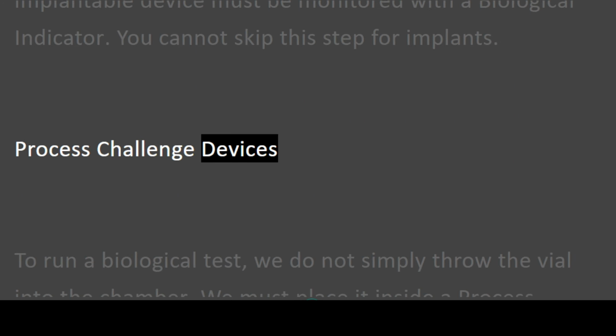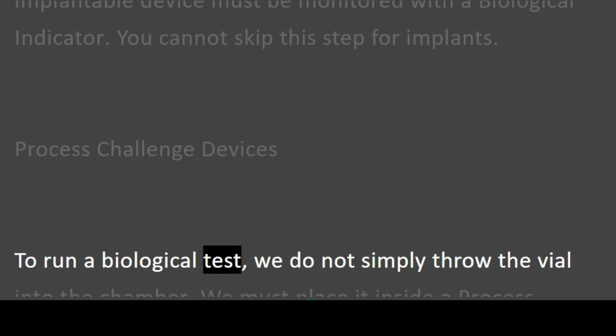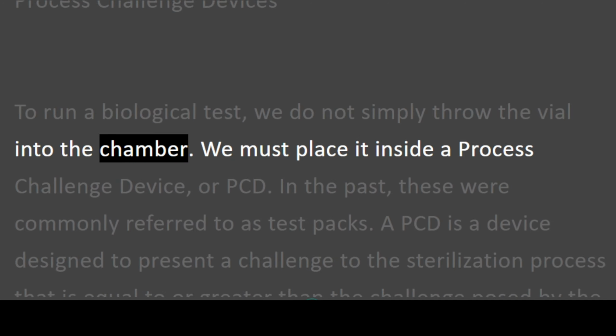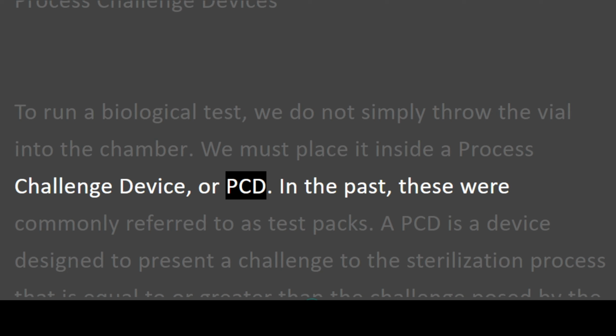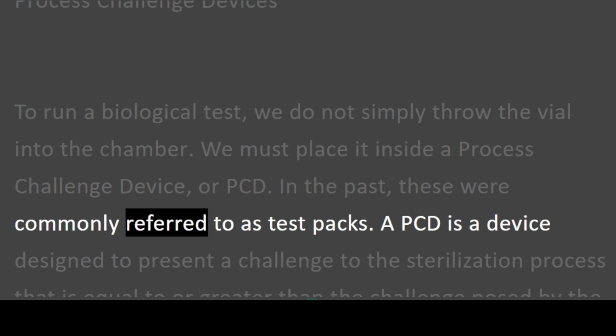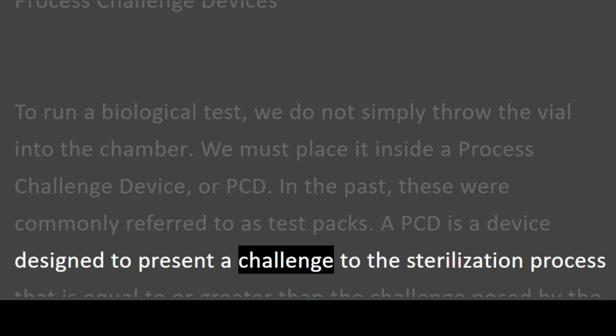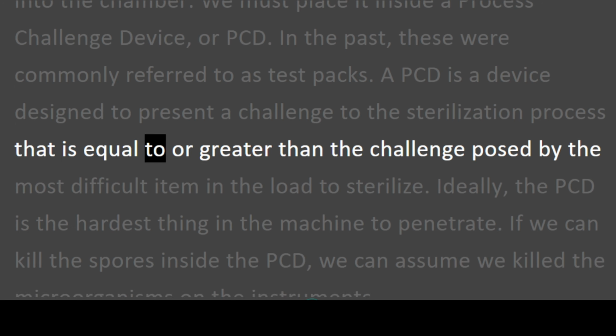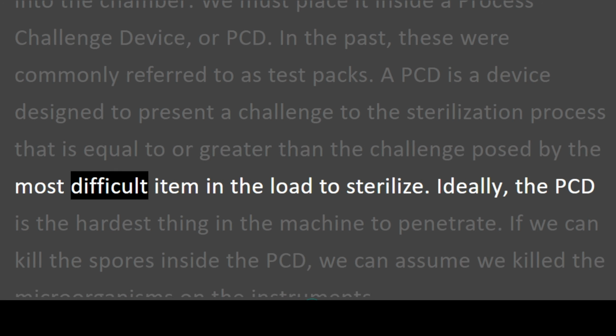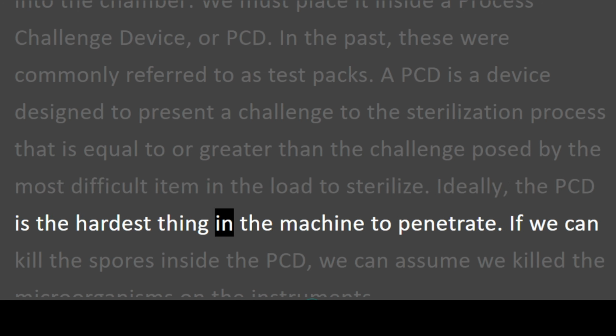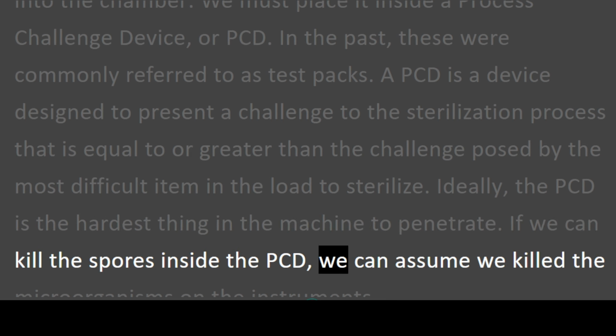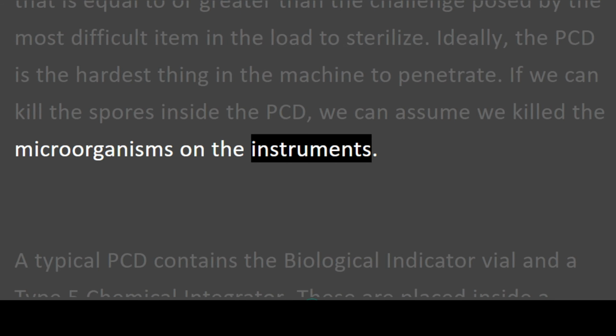Process challenge devices. To run a biological test, we do not simply throw the vial into the chamber. We must place it inside a process challenge device, or PCD. In the past, these were commonly referred to as test packs. A PCD is a device designed to present a challenge to the sterilization process that is equal to or greater than the challenge posed by the most difficult item in the load to sterilize. Ideally, the PCD is the hardest thing in the machine to penetrate. If we can kill the spores inside the PCD, we can assume we killed the microorganisms on the instruments.